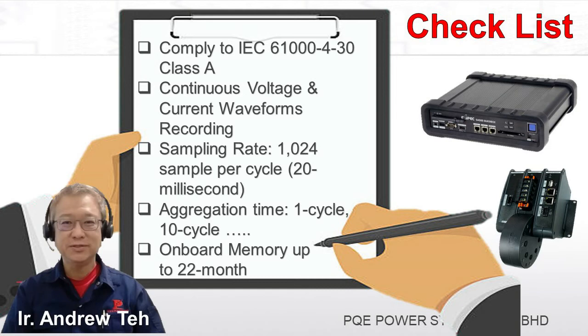For a correct and accurate power quality voltage dip study, we need a power quality analyzer with 6 major features. Feature 1: the analyzer must fully comply with IEC 61000-4-30 Class A. Feature 2: it must be able to continuously record three phases of voltage and current waveforms throughout the power quality recording period, up to 22 months, to ensure no missing event recording. Feature 3: it must come with a sampling rate of 1024 samples per cycle — i.e., 1024 samples logged within 20 milliseconds for 50 Hz supply frequency — throughout the recording period up to 22 months, to capture detailed power quality events.